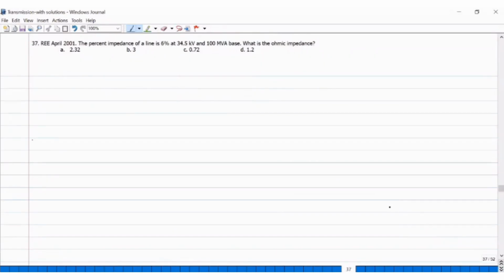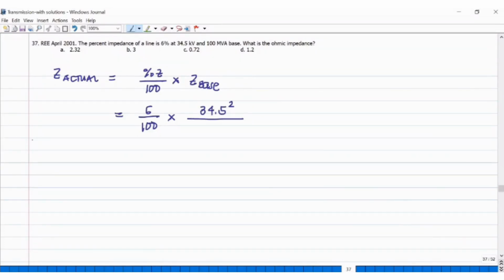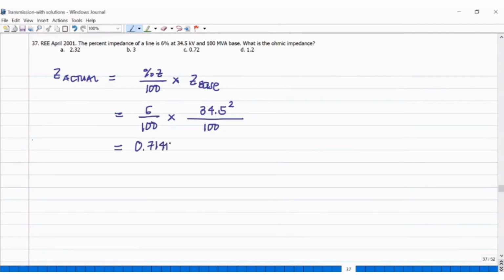37, the percent impedance of a line is 6% at 34.5 kV and 100 MVA base. So what is the ohmic impedance? So yung parang actual. So percent Z over 100 multiplied by Z base. So that is 6 over 100 multiplied by yung pag-compute natin ng Z base. So 34.5 squared divided by 100. Naka-MVA na siya. Wala na tayong factor na i-divide or i-multiply. 6 divided by 100 times 34.5 squared divided by 100 is equal to 0.71415 ohms. So I will choose 0.72.